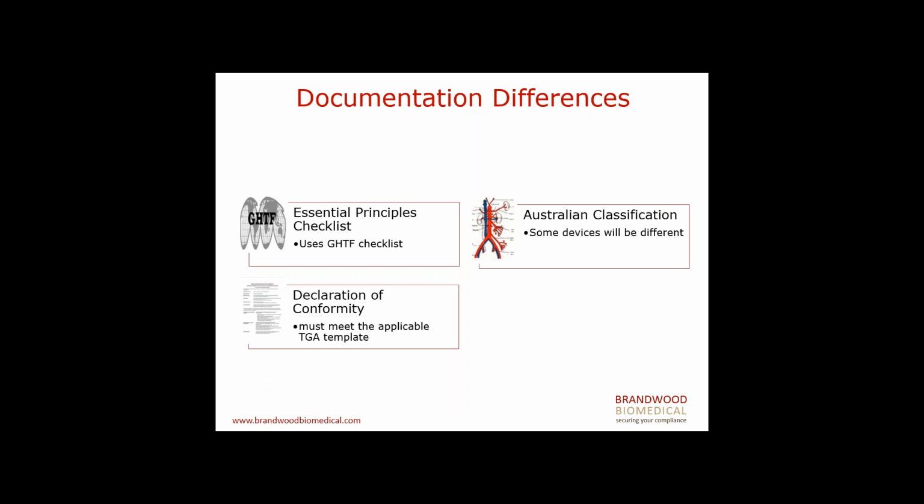TGA have their own Declaration of Conformity, and they will not accept that from Europe. They won't accept a European declaration. There are templates available, but basically you have to submit an Australian Declaration of Conformity.